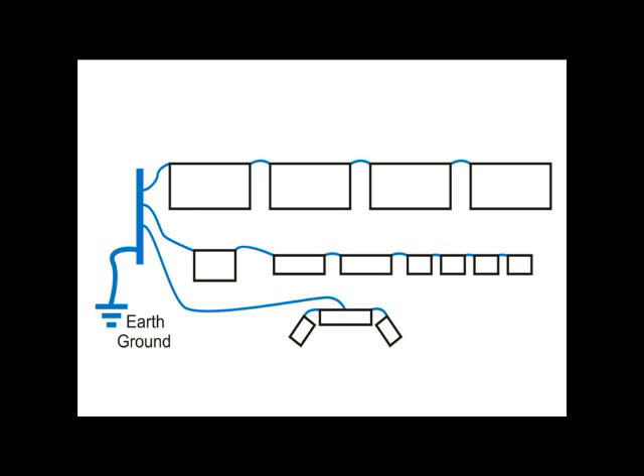It has lots of equipment, and what I want to point out here is notice the blue lines. Those are the grounds from each cabinet, and they are all connected in one direction toward that blue ground bar at the left, and that goes outside to the earth ground.